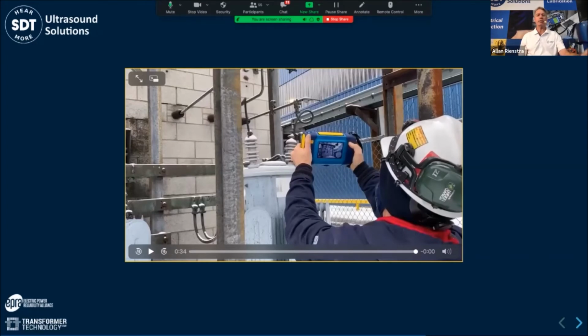But then what it does is when it hears the ultrasound, it also has a camera on it, a visual camera. So on the backside, the inspector is able to look at the screen, just as Craig is doing here in the picture. And if there's any source of partial discharge, it will show up as an overlay where it is. So we're able to hear it, see it, and pinpoint exactly where it's coming from on the asset.